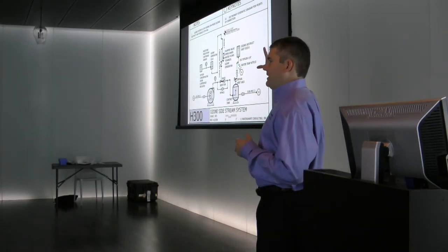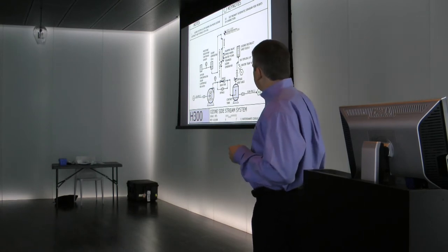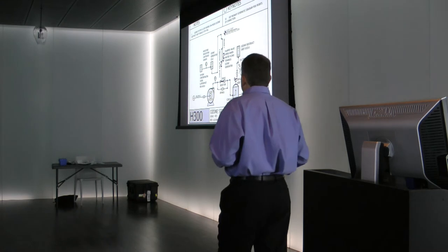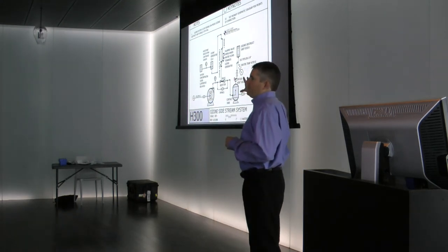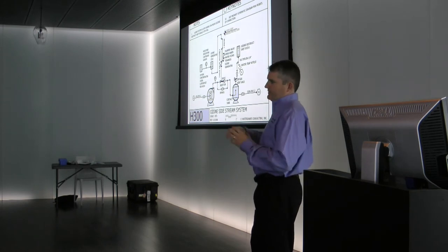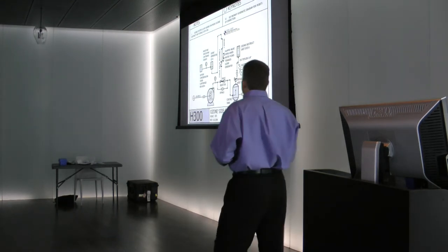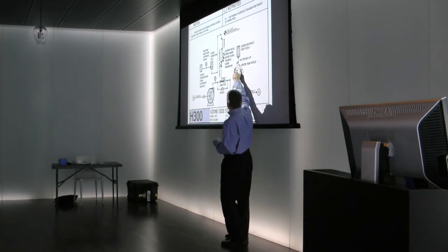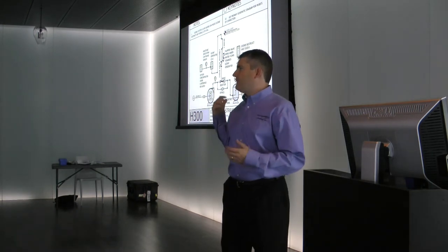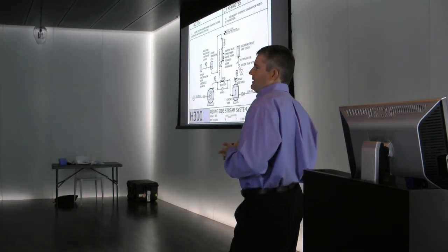Inside there, now there may be moisture coming up through there because the ozone just left the water, and there may be water that gets up into the system. So there's usually a little heater in there to keep the carbon dry. And to make sure that we don't get any water up there, we have this water trap detail. The manufacturers basically have it down to a little part that you buy now, and you just plumb it in. What it does is it ensures that if any water got up into the system, it would fall out and go through a drain as opposed to going up into the unit where you've got the carbon. So that guarantees that you're not going to have an issue with the off-gas destruct unit.